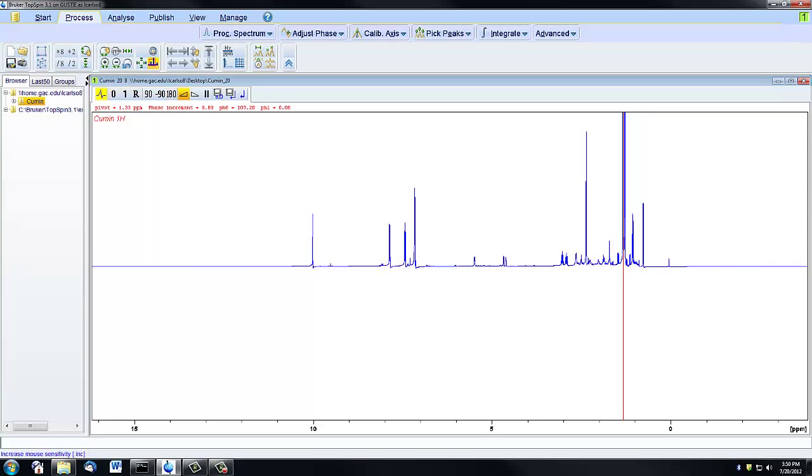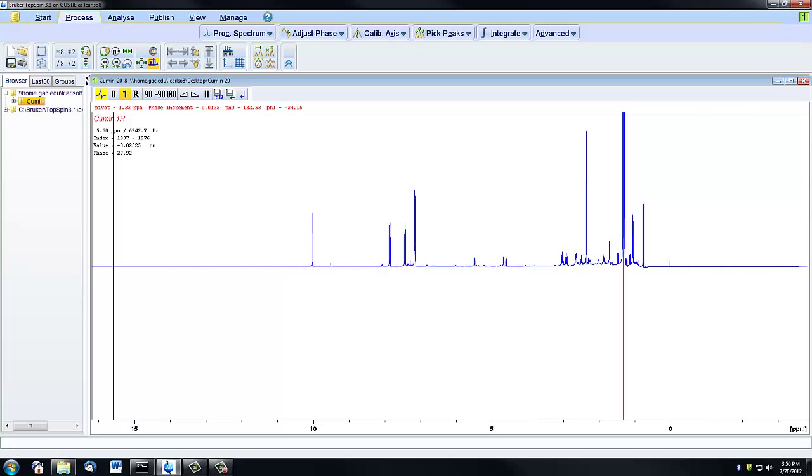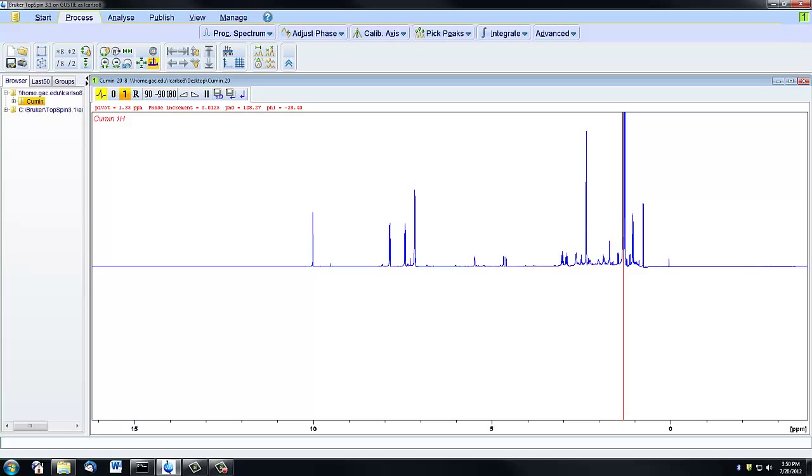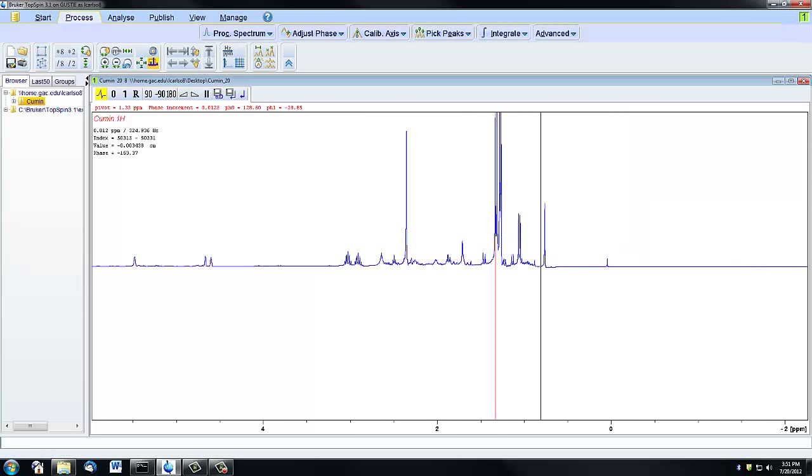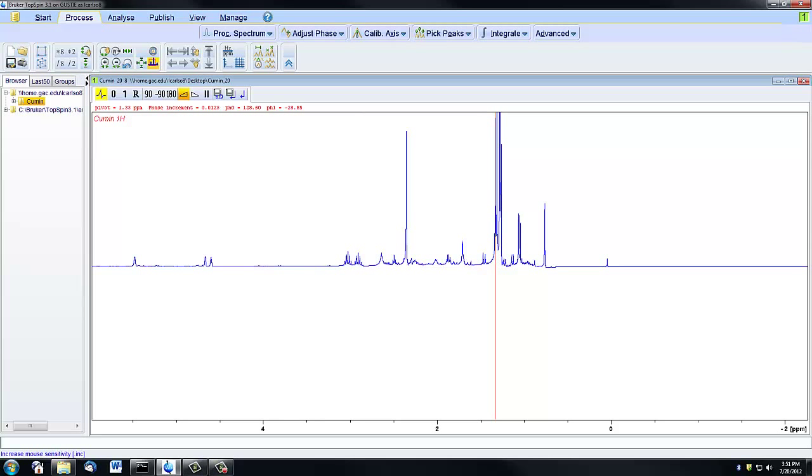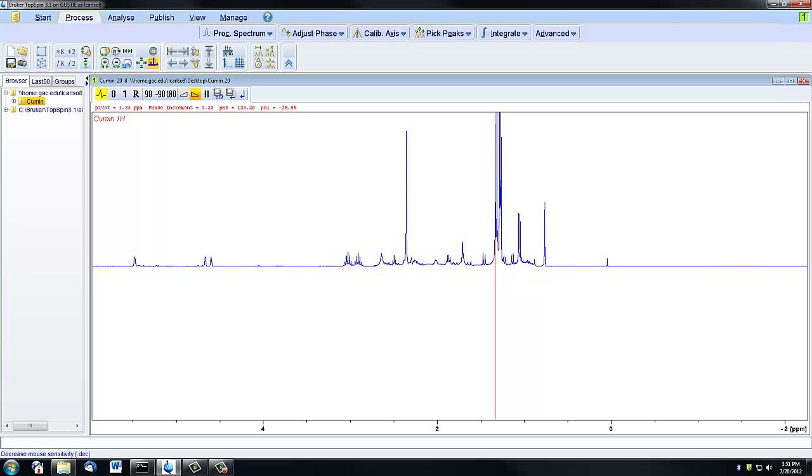Conversely, if you use the downward slope, click that a couple of times and go back and do a first order correction, I'm moving the mouse a lot but the spectrum is not moving very quickly. So it can be helpful to use the coarse adjustment first and then maybe zoom in. Here I can show you if I zoom in on this part of the spectrum, maybe do some coarse adjustment first, and then when it looks pretty good to me, I might switch to a finer adjustment and try to really make small changes in the zoomed-in version.